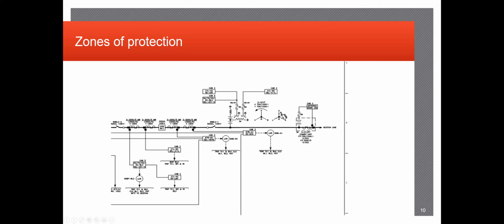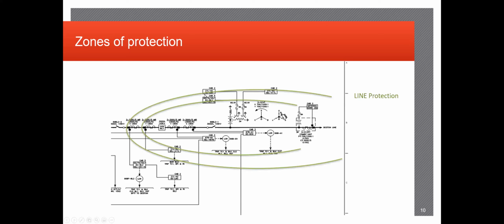So in this module, we're kind of looking at the zones of protection, in which case for here, we are going to be, I gotta go next slide. There we go. We're going to be indicating which zone is which. So right here, we're looking at the line protection in these green circles. The outermost circle is your primary source of line protection. When you're looking at relay one line, you'll notice that the primary relay is always on the outermost CT of the breaker. And the innermost circle here coming off the secondary CT is actually your secondary relay for your redundant backup protection.